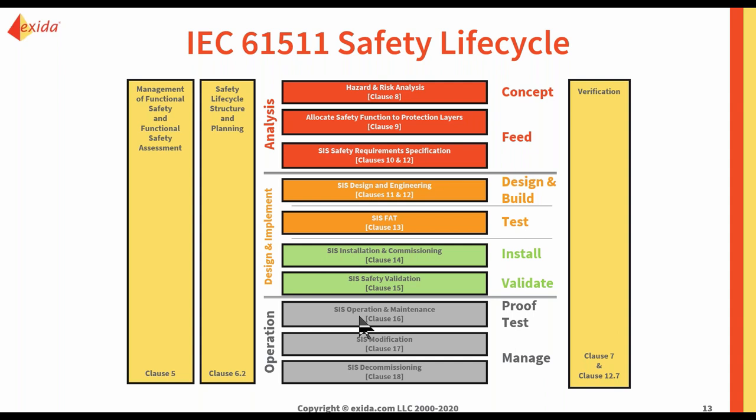And this whole lifecycle details how to, first of all, formulate the concept and the specification of your SIS, and then start building and designing it, test it, install it and validate it, and then start operating using the SIS. During the operation time, you have different kinds of proof testing for maintenance, and you manage all the modifications. And finally, it would be the decommissioning of the SIS. So it describes the whole life of the SIS system. That's why it's called a lifecycle.